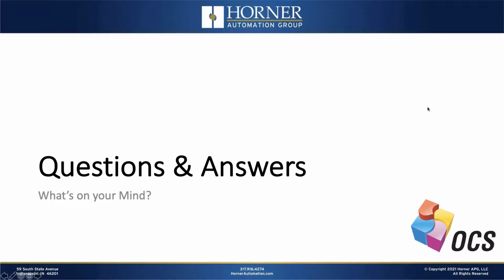The answer to that is currently the first 20 messages are retained and all messages after that are lost. So I'm sure that's an area where we will update our MQTT driver to probably do a little more buffering, and we may even look at making it a circular buffer. We've had some requests come in from specific customers, and I'm sure we're going to honor those requests, as we always are trying to make our products better.